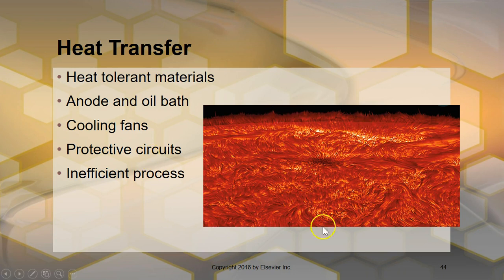And in case you don't notice, this is a big old ring of fire right here. Now, your machines that you work with should never have that type of radiation, but you need to understand that all of that can actually occur if you don't treat your equipment correctly. Modern X-ray machines have protective circuits that are built in, and it keeps you from using unsafe exposure techniques, and it'll keep you from actually overloading the tube.